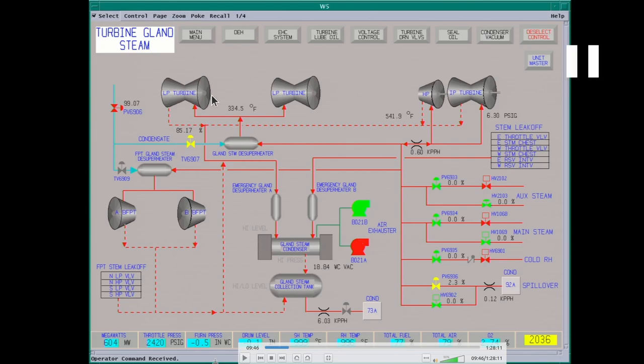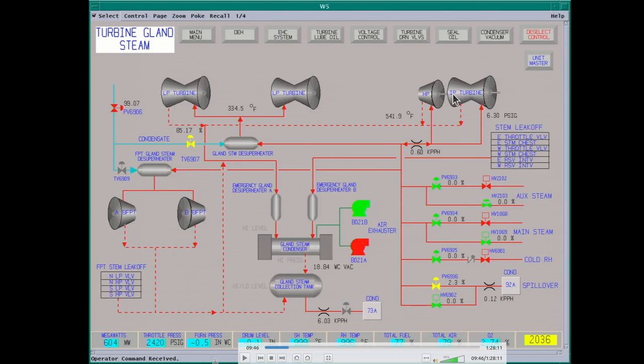Coming up on the gland steam system — this is the gland steam. Usually you start out with aux steam, which provides steam to seal your turbine so you can pull a vacuum on it. If you didn't, air would come in past the shaft seals and you wouldn't pull a vacuum. This unit becomes self-sealing at higher loads — there's enough leakage steam off the high-pressure and intermediate-pressure to seal the low pressure. But you start with aux, then go to main steam once you get some boiler pressure built up, then to cold reheat as normal makeup. When you're self-sealing, there's excess steam, so it goes to spill-over which dumps it back to the surface condenser.